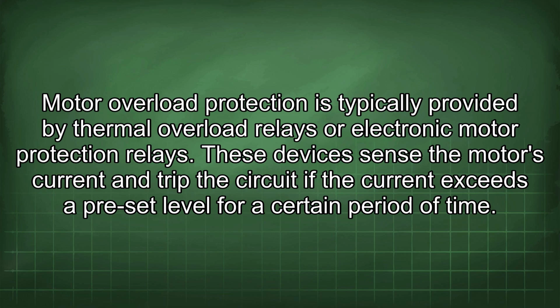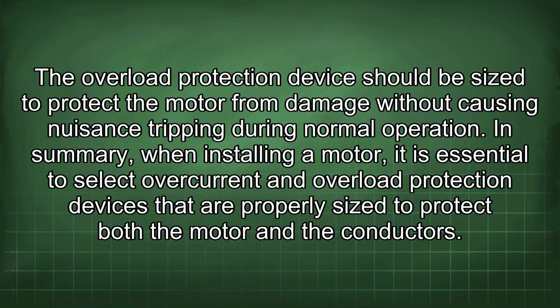These devices sense the motor's current and trip the circuit if the current exceeds a preset level for a certain period of time. The overload protection device should be sized to protect the motor from damage without causing nuisance tripping during normal operation. In summary, when installing a motor, it is essential to select overcurrent and overload protection devices that are properly sized to protect both the motor and the conductors.